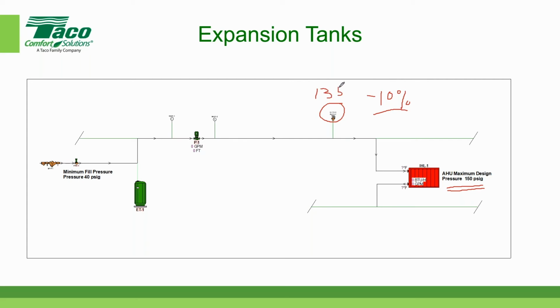Now, safety relief valves are a very simple device. Basically, it's a valve with a spring and a disc. And if you get close to the setting of the safety relief valve, they can drip or weep or leak a little bit. So we want the piping system that's connected to the safety relief valve to not have a pressure greater than 130 pounds. So I'm just making it 5 pounds less. You could make it 10 pounds less, but I'm making it 5 pounds. So it's 130 pounds at the piping system.